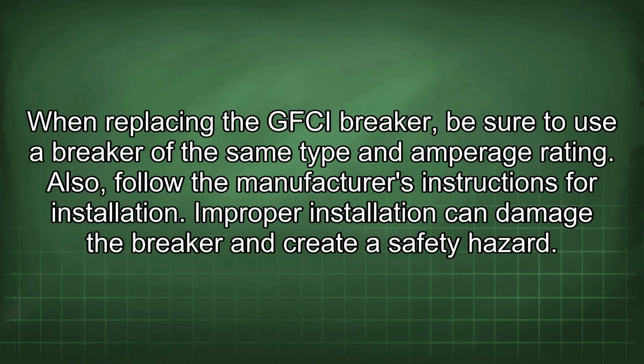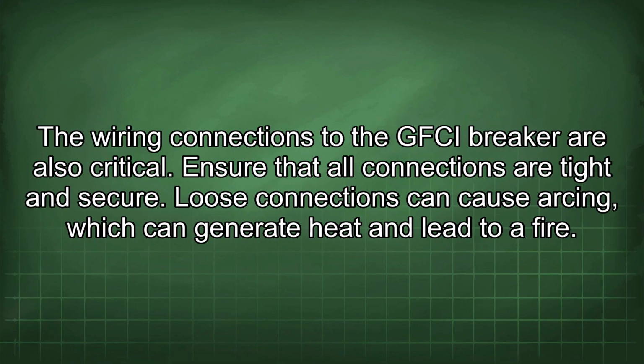When replacing the GFCI breaker, be sure to use a breaker of the same type and amperage rating. Also, follow the manufacturer's instructions for installation. Improper installation can damage the breaker and create a safety hazard. The wiring connections to the GFCI breaker are also critical. Ensure that all connections are tight and secure. Loose connections can cause arcing, which can generate heat and lead to a fire.